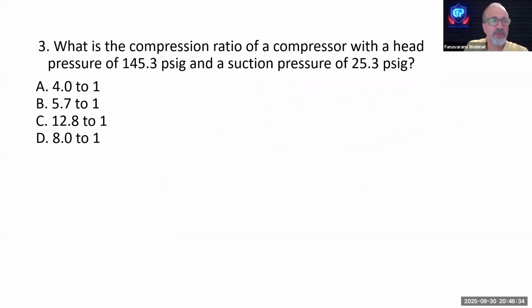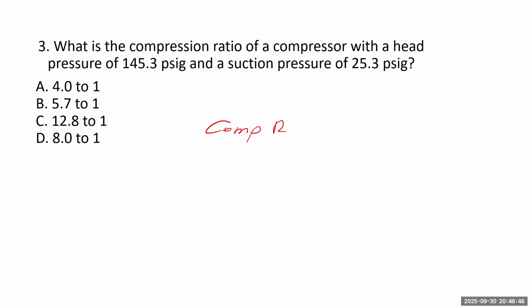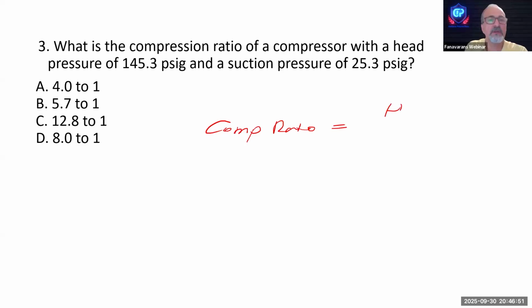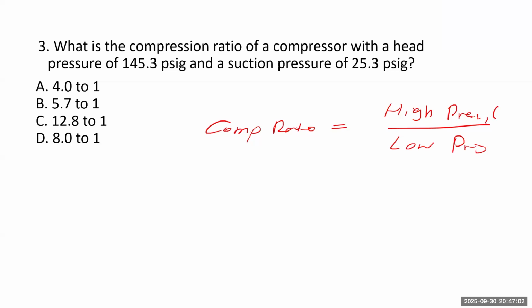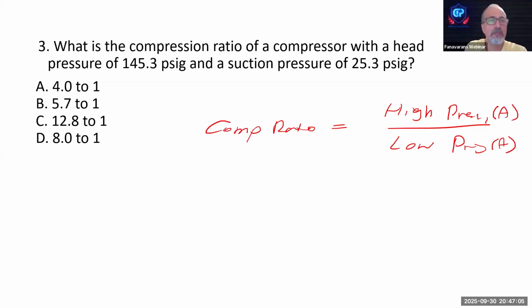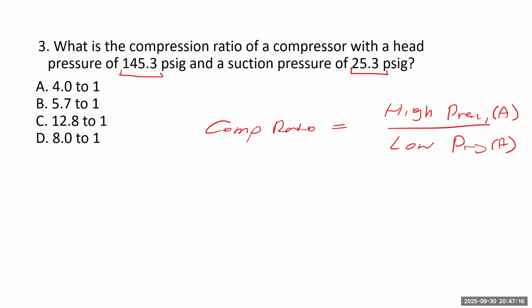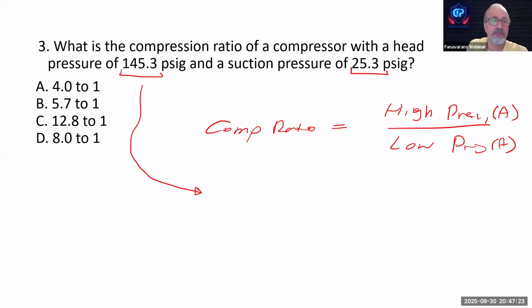Question number 3, what's the compression ratio of the compressor? Anybody knows what a compression ratio is? The definition of the compression ratio? Yeah, compression ratio is the high side pressure divided by the low side pressure, in absolute scale. So we have the high side 145.3 and the low side 25.3. But you are not supposed to divide these numbers directly. You need to convert them to the absolute scale.